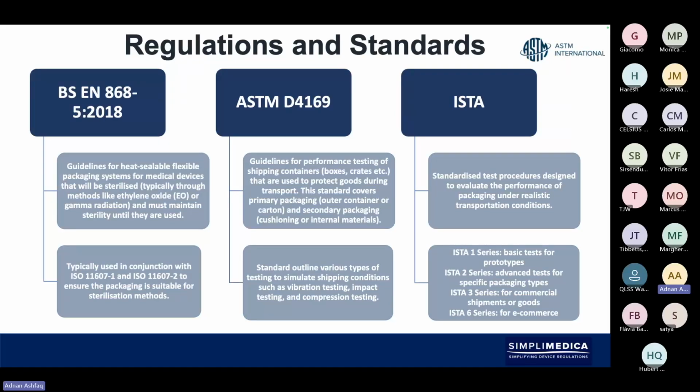And then, of course, there's different types of sterilization which the device would undergo, which could be ETO, ethylene oxide, or gamma radiation. These are the two popular ones. And that's also got to be considered because there's an effect that the radiation can actually have on the seal.